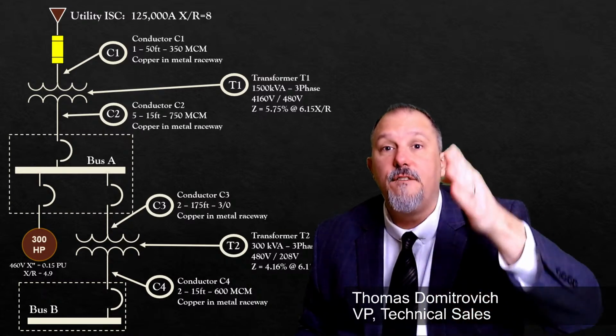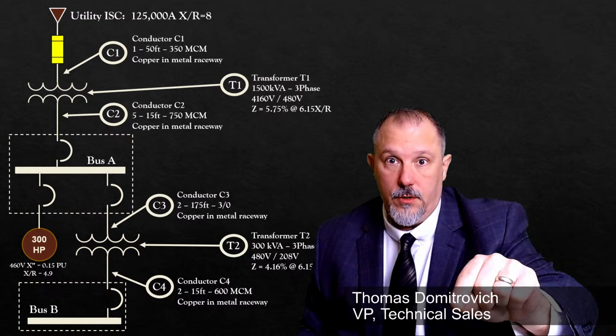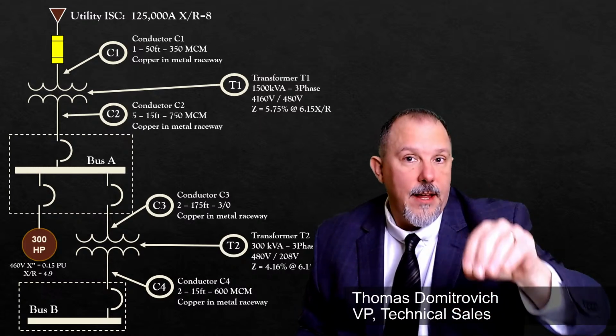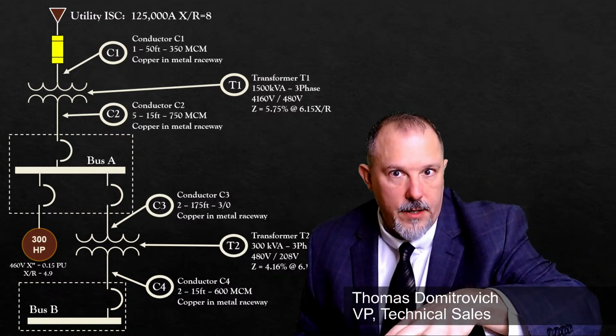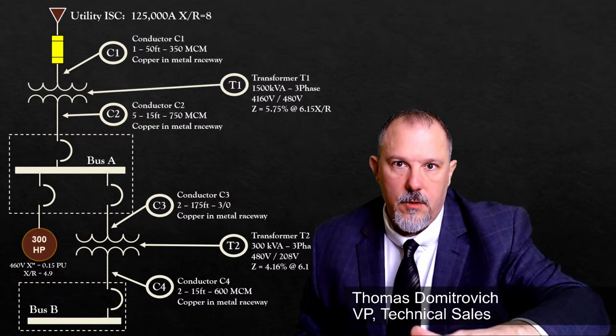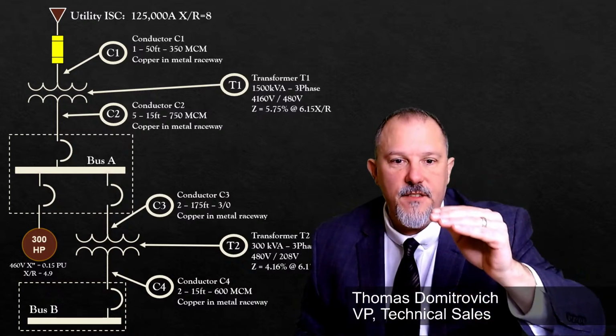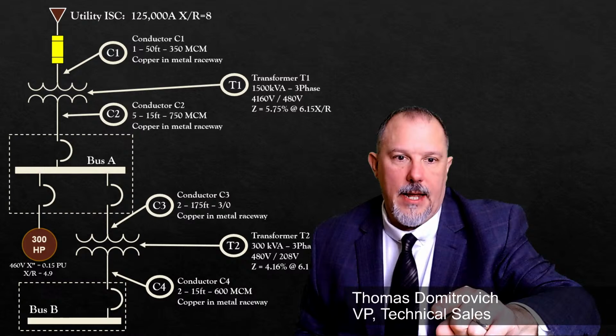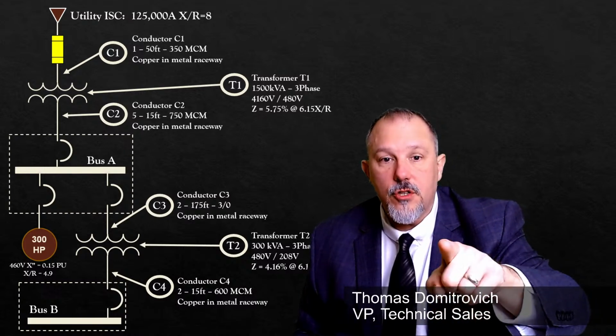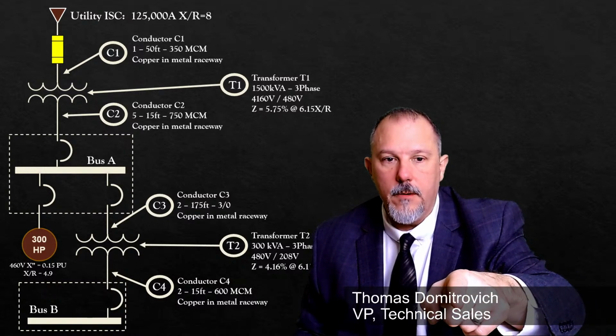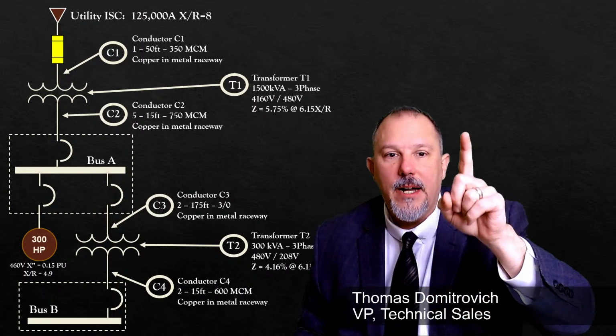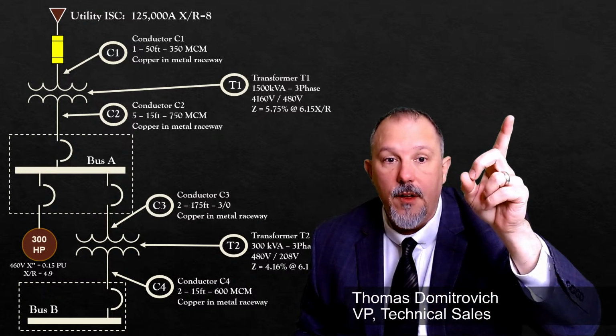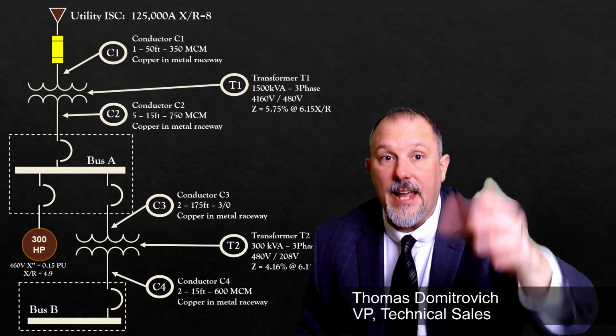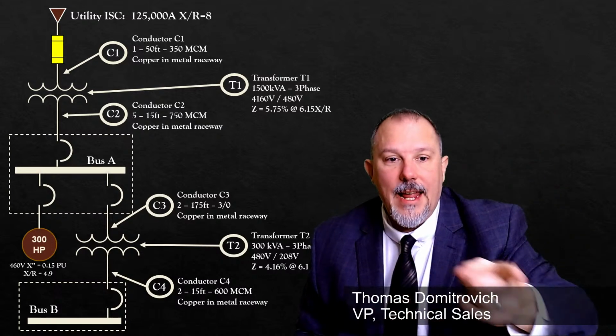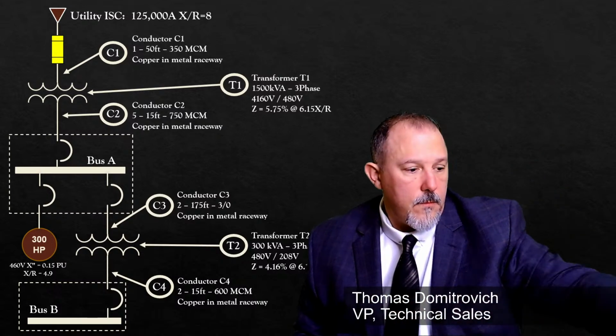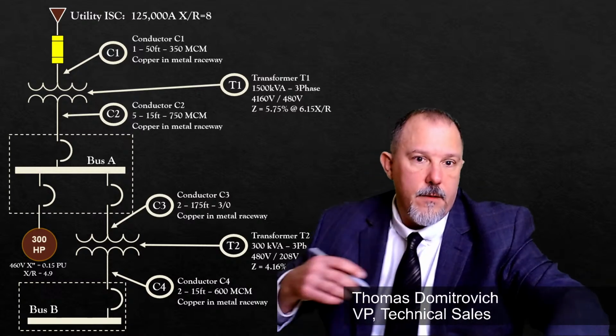Whatever fault current flows to feed that fault, remember, current is comprised of electrons, and electrons are party animals. Okay, when there's a party, when there's an event going on, they all want to get there. The fault current that flows through the conductor feeding that transformer is going to be comprised of the fault current that's flowing through the main on bus A, because I've got the utility, and the motor contribution.